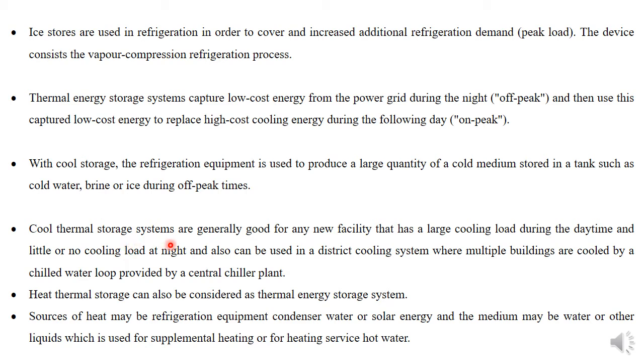Cool thermal energy storage is good for a facility that has a large cooling load during the daytime and little or no cooling load at night. It can also be used in a district cooling system, where multiple buildings are cooled by a chilled water loop provided by a central chiller plant, meaning this thermal energy storage is used hybrid with the chiller during the day. Heat thermal storage can also be considered a thermal energy storage system.